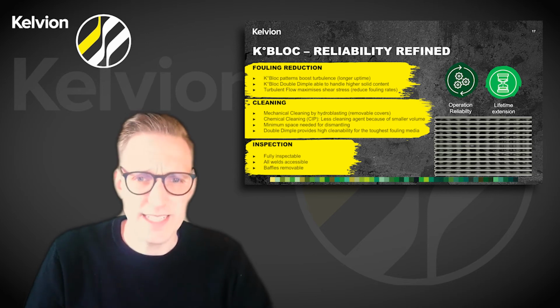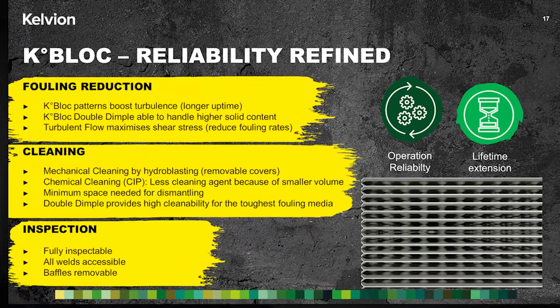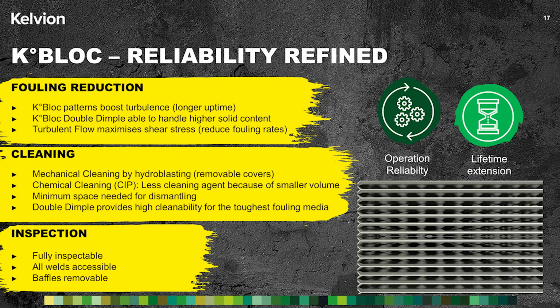In the beginning, we have said that the operational reliability is important for any process equipment. The K°Bloc can reduce, due to its plate design, fouling, which is the main threat for service interruptions. The high shear stress, which we always consider in our designs, reduces the fouling tendency. After a while, fouling will occur anyway, but then the K°Bloc offers the possibility to clean the plate pack entirely by mechanical means, for example by hydroblasting. But also chemical cleaning is always a good option. While the heat exchanger is open for cleaning, a thorough inspection for corrosion or blocking solids can be done as well. Keep in mind that all welds are inspectable, accessible, and repairable at this stage.